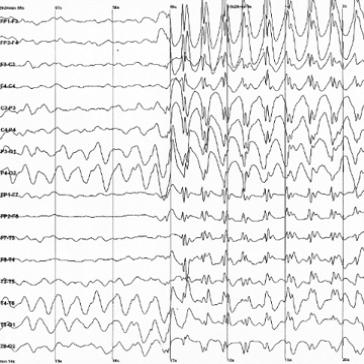Since an EEG voltage signal represents a difference between the voltages at two electrodes, the display of the EEG for the reading encephalographer may be set up in one of several ways. The representation of the EEG channels is referred to as a montage. Sequential montage: each channel, i.e., waveform, represents the difference between two adjacent electrodes. The entire montage consists of a series of these channels. For example, the channel FP1-F3 represents the difference in voltage between the FP1 electrode and the F3 electrode. The next channel in the montage, F3-C3, represents the voltage difference between F3 and C3, and so on through the entire array of electrodes.